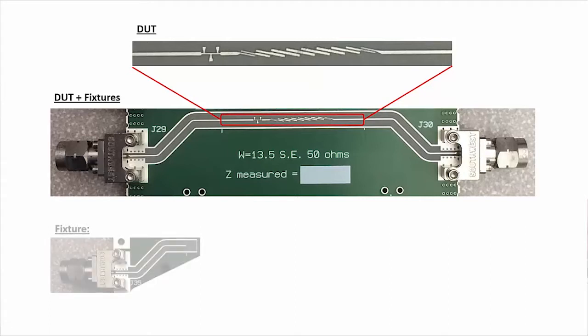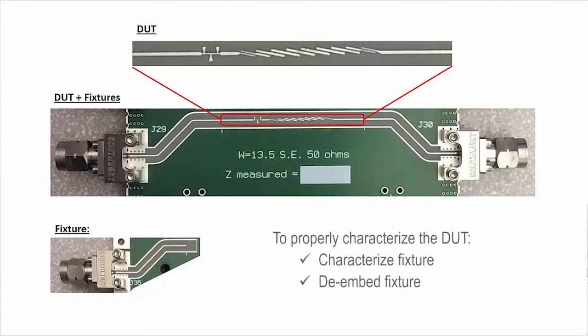Also on the validation board, I've built a replica of the fixture with connectors. To properly characterize the DUT, I will need to characterize the fixture and then de-embed the fixture at each port of the DUT from the combined measurement of the DUT plus fixtures.